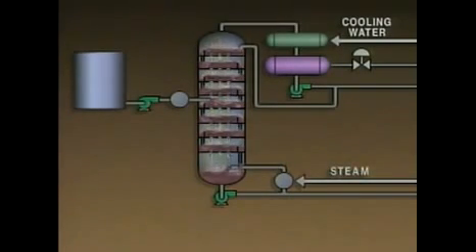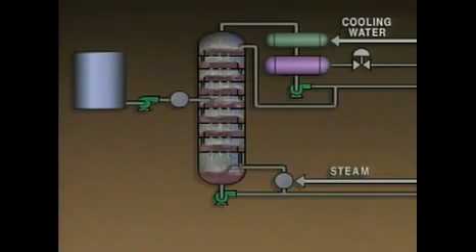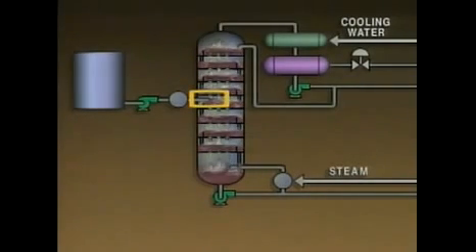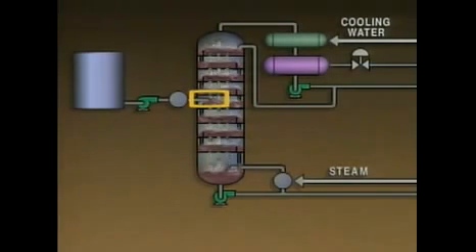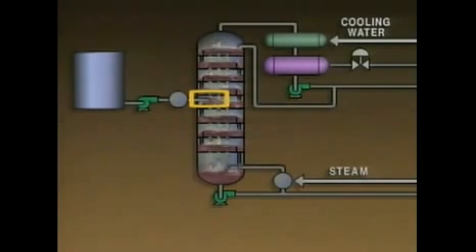Changes in the differential pressure may indicate that a problem exists. For example, an increase in differential pressure could be an indication that the feed rate is too high. Too much feed entering the tower will overload it. If this happens, the differential pressure will increase and the tower will be unable to make the desired separation. In this case, it might be necessary to decrease the feed rate.